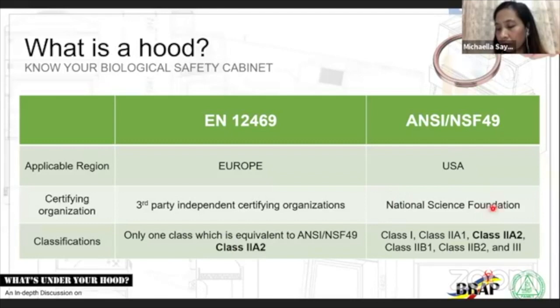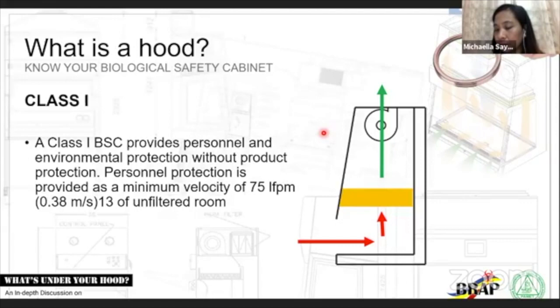Now, for EN 12469, there's only one class of biosafety cabinet, which is equivalent to your class 2A2 under the ANSI NSF 49 standards. Okay. So if you're buying your biosafety cabinets and you just say class 2, you might get a biosafety cabinet that is rated for EN 12469. But if you specify class 2A2, you most probably will get the NSF 49 certified biosafety cabinet. So the most common here in the Philippines is your NSF 49. So we will just focus on the classes defined under that standard.